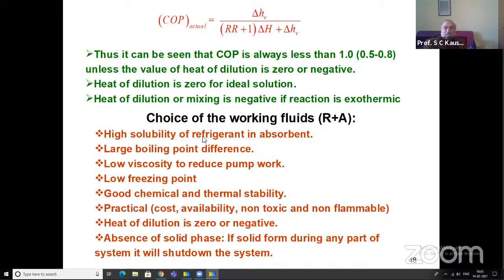Other characteristics which are desirable for the choice of the refrigerant and absorbent pairs are as mentioned here. There must be high solubility of the refrigerant in the absorbent, a large boiling point difference between the refrigerant and the absorbent, low viscosity to reduce the pump work, low freezing point, and good chemical and thermal stability. Practically, cost should be low, availability should be high, and the refrigerant should be non-toxic and non-flammable. Heat of dilution is 0 or it should be negative. So delta H should be negative. It is desirable. We have seen that only if delta H is negative is COP actual greater than 1.